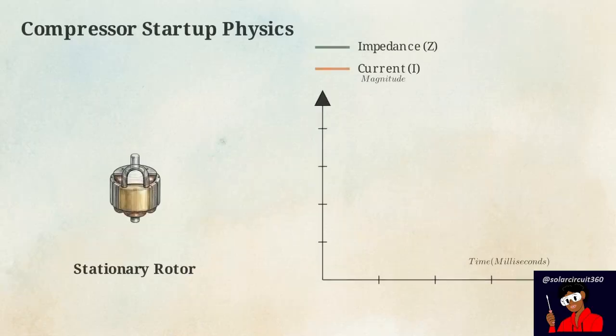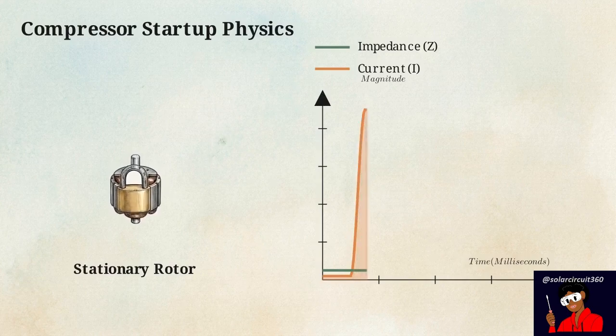Inside every refrigerator is a compressor, and inside that compressor is a physical AC motor responsible for pumping refrigerant. Electrically, this makes the compressor an inductive motor load. At exactly time zero, before the thermostat clicks, the internal rotor is completely stationary. The motor's electrical impedance, shown on the baseline, is practically zero.